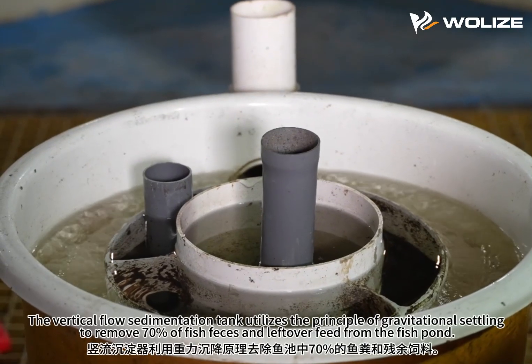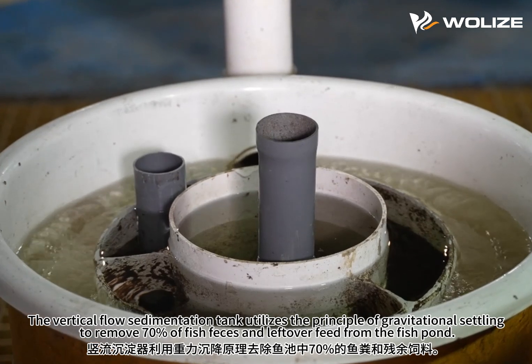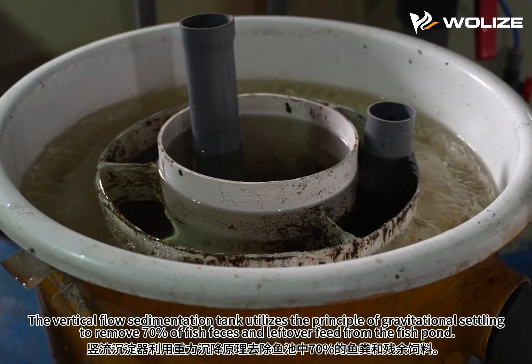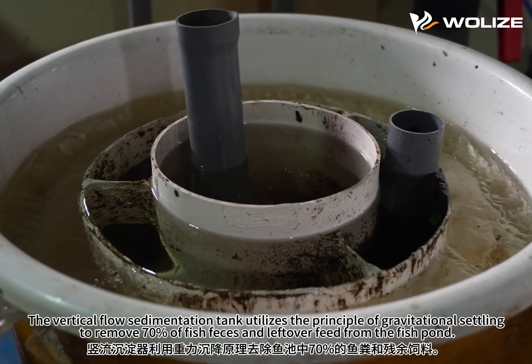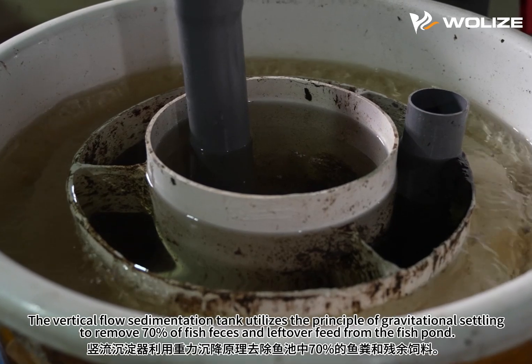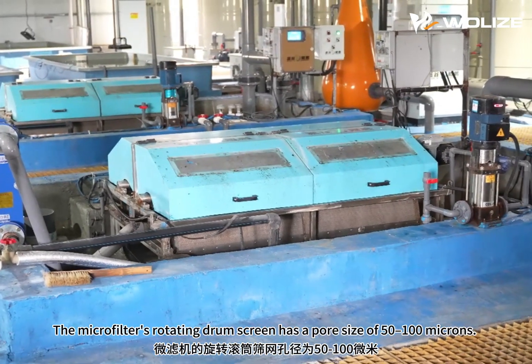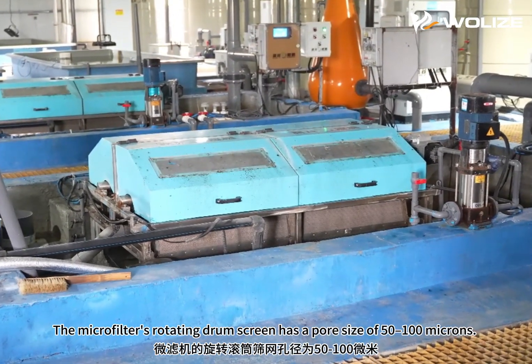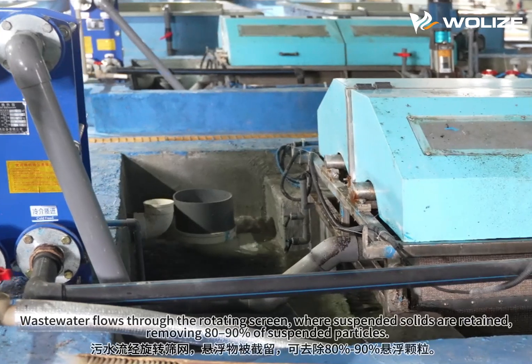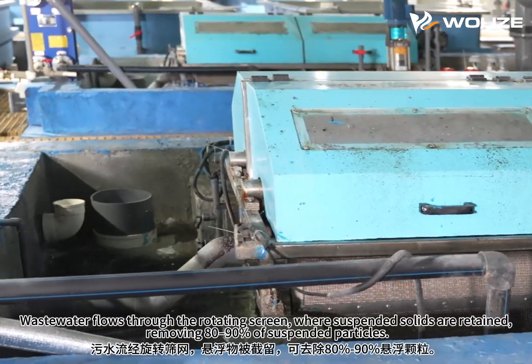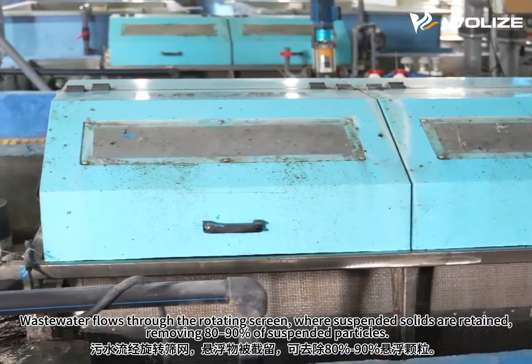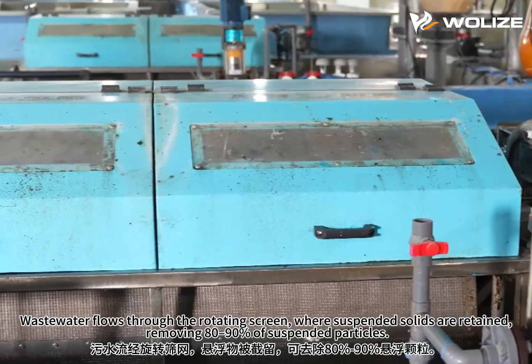The vertical flow sedimentation tank utilizes the principle of gravitational settling to remove 70% of fish feces and leftover feed from the fish pond. The microfilter's rotating drum screen has a pore size of 50 to 100 microns. Wastewater flows through the rotating screen, where suspended solids are retained, removing 80 to 90% of suspended particles.